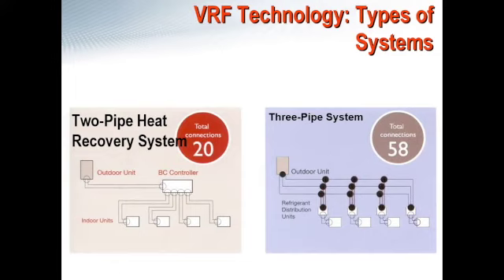When you're looking at a two-pipe system, this is a heat recovery system with your outdoor unit, your BC controller, and all of your 4 zones served on the indoor units. You're going to have connections at the BC controller and only the BC controller to the indoor units. That's going to give you a total of 20 connections on a two-pipe system. The same system with 3-pipe connections and individualized distribution boxes to each of the 4 indoor units serving the spaces is going to exceed that number of connections. We show 58 here, and that's just on a 4 indoor unit system. It's obviously going to be amplified as the system grows in size.